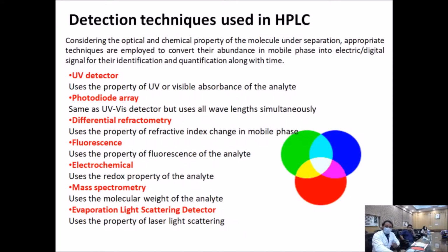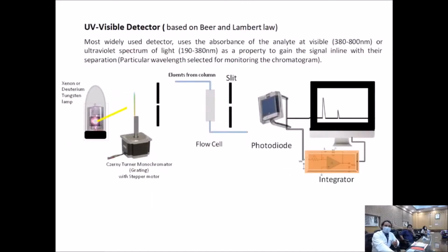I have a pictorial representation here for the individual UV visible detector, in which monochromatic light is produced from the deuterium or tungsten lamp. It is passed through and falls on the eluent as it passes through along with the effluent. It gets absorbed, and the absorbed light is digitalized using a photodiode.